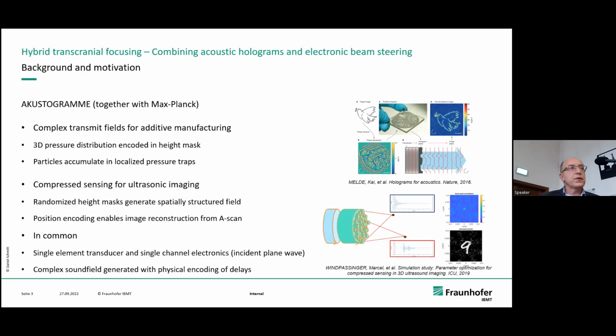On the other hand side, we are interested in imaging again, and we are using a randomized mask here. So the same system, single element transducer, mask in front of it, but that's not structured, that's unstructured actually. And it's producing a very diverse ultrasound field. So you will get a different response from any point in the field. And if you know that response, then you can guess where the signal is coming from. So the idea is to recover the whole acoustic signal from a single A scan. And we currently managed to do that with some very easy phantoms like letters and those figures. And we are on the way to implement that also in medical beamforming.